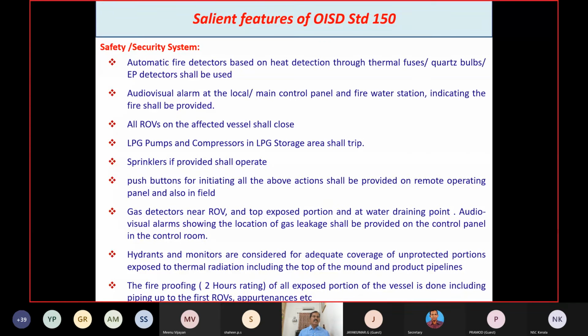Suppose in case of any emergency you operate the ESD, what will happen? All ROVs on the affected vessel will close immediately, and the power supply to the prime movers, that is LPG pumps and compressors in the LPG storage area, will trip automatically. Sprinklers, if provided in the system, shall operate automatically, and the siren will also start sounding. Push buttons for initiating all the above actions shall be provided on the remote operating panel and also in the field. So we can operate from the field itself and also from the remote.